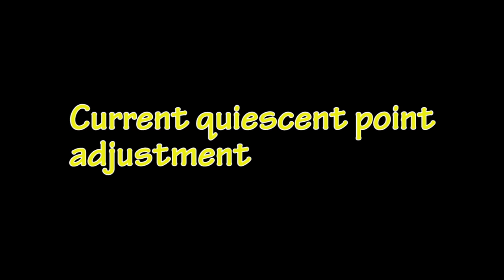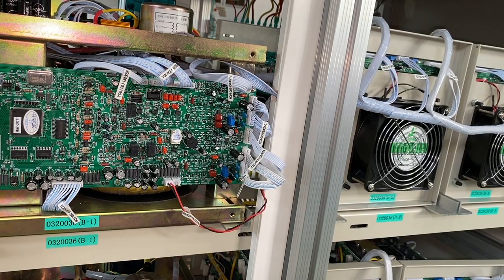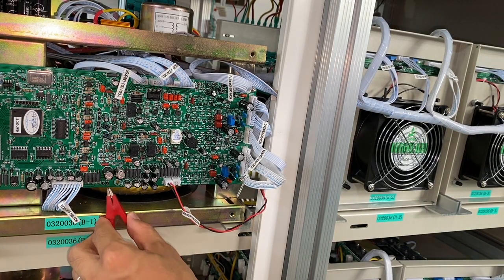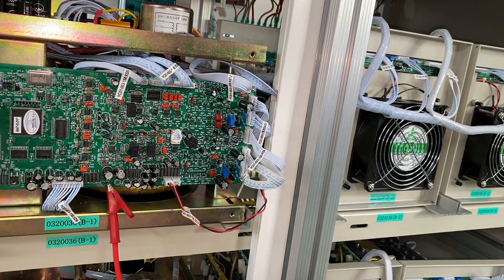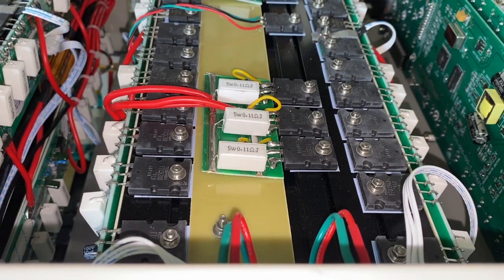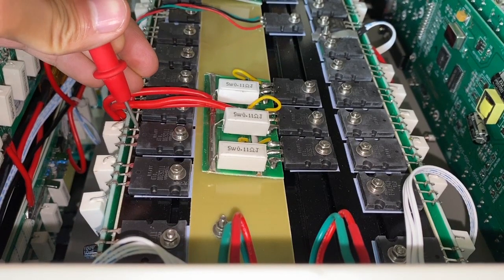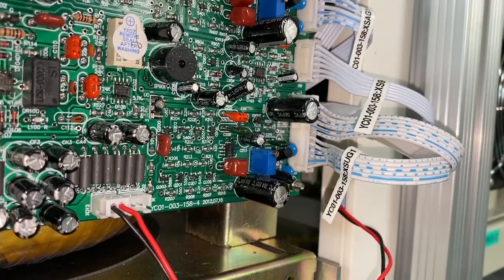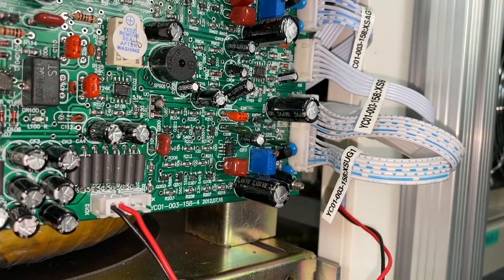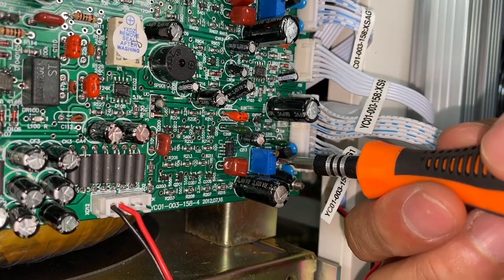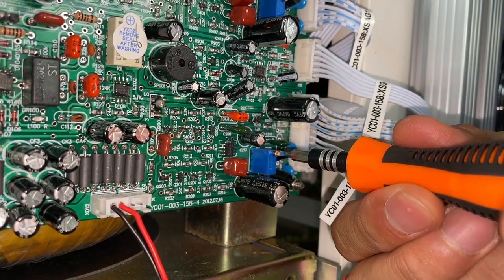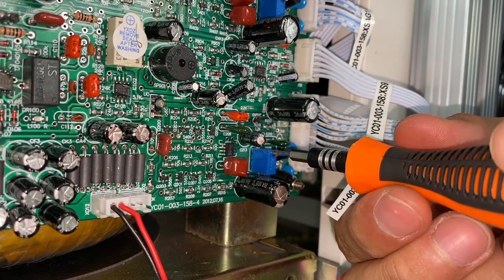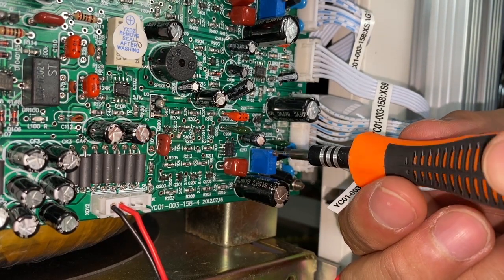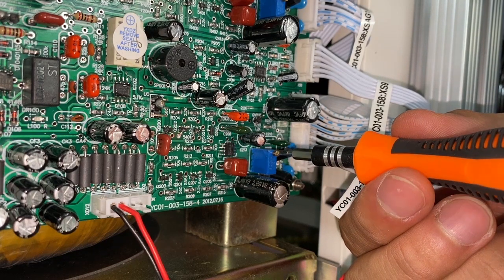Current quiescent point adjustment. The following video will demonstrate how to make the adjustment. Multimeter negative probe placed on the main board JD11. The positive probe placed on the first feet of the current transistor. Locating the current potentiometer. Turning the potentiometer clockwise to increase the value. Turning counterclockwise to decrease the value.